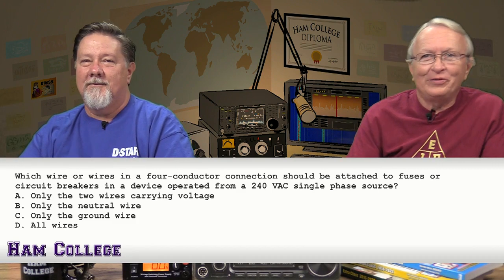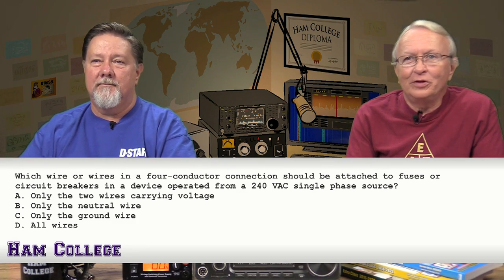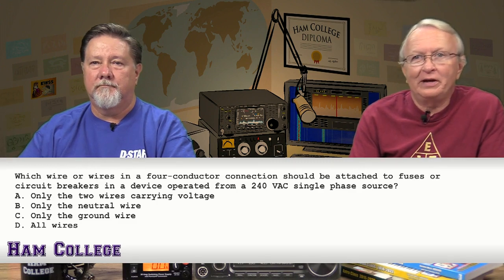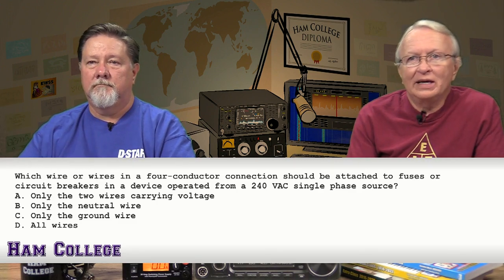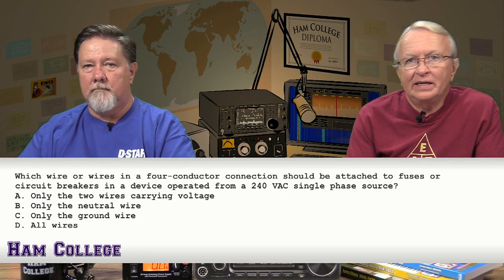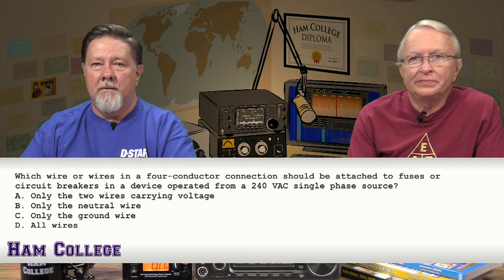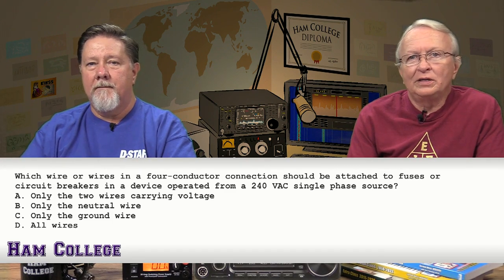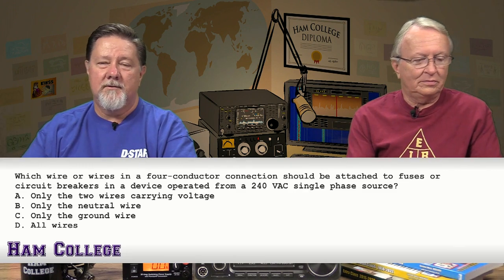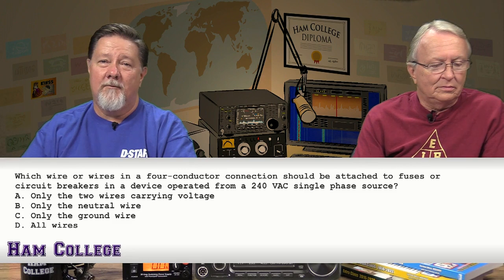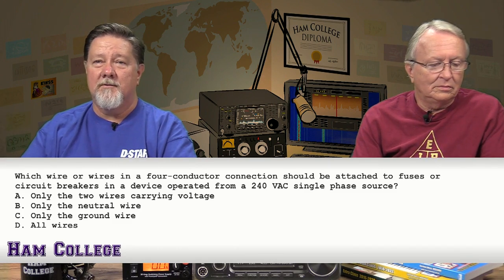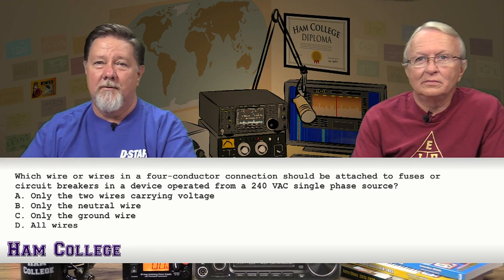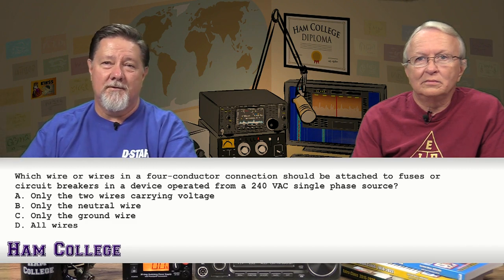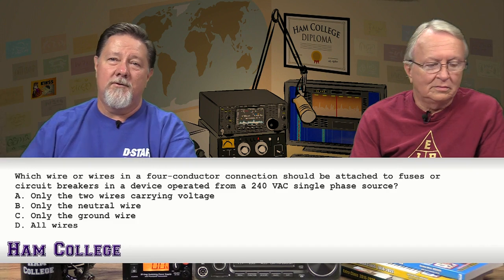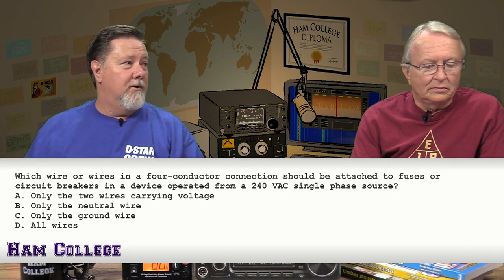Which wire or wires in a four-conductor connection should be attached to fuses or circuit breakers in a device operated from a 240 volt AC single-phase source? A, only the two wires carrying voltage. B, only the neutral wire. C, only the ground wire. Or D, all wires. I can tell you right now, it's not all wires. Don't hook them all up to the circuit breaker. And don't do C, don't hook the ground wire up to it. And don't do B, don't hook up the neutral wire either. The answer is A, only the two wires carrying voltage attached to the circuit breakers.